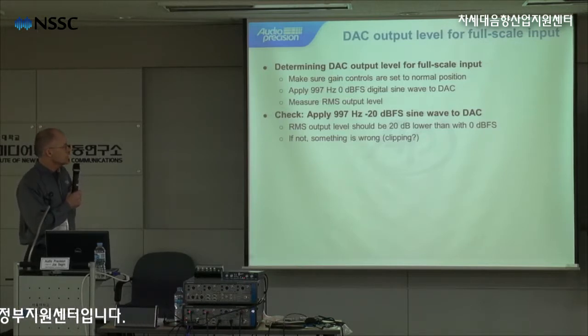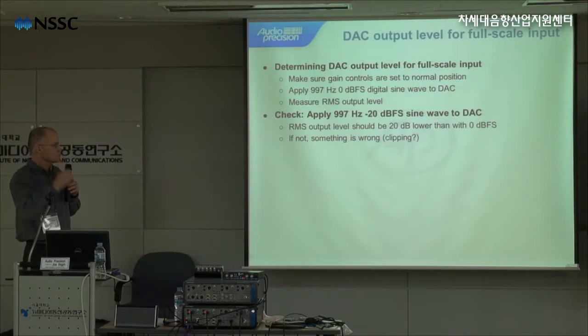Now, determining the DAC output level for full-scale input. With the digital to analog converter, you would want to make sure the gain controls are set to the normal position. Apply a 997 Hertz 0 dBFS digital sine wave to the DAC and measure the RMS output level. As a check, you can apply a 997 Hertz minus 20 dBFS sine wave to the DAC, and the RMS output level should be 20 dB lower than with 0 dB. If not, something is wrong.